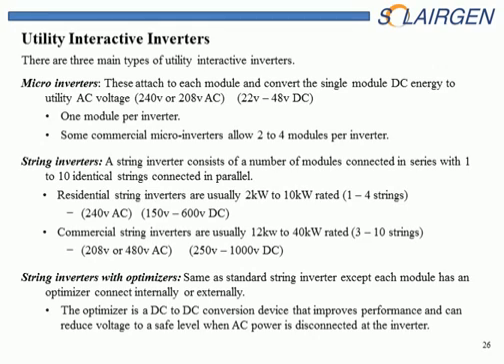String inverters, it depends on what type of string inverter it is, but the typical residential string inverter can be anywhere from 150 to 600 volts. These are the older models. The newer models, the Solar Edge with PV optimized strings, drop down to 1 volt with a power outage. So they're just as safe as microinverters.